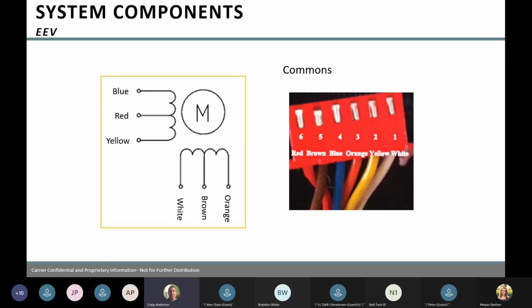So here's what we're going to be looking at on your plug. Like I said, it's going to be 6 wires coming out of that EE valve. You'll notice here on number 5, as I stated, if you're pulling the wires, that number 5 has been pulled out a little bit. So now when they're going to plug that back in, chances are that's going to push out a little bit farther. So always be mindful of your plugs before you plug them back in. 5 and 6 is your common. Blue, orange, yellow, and white are our power going to our EE valve.